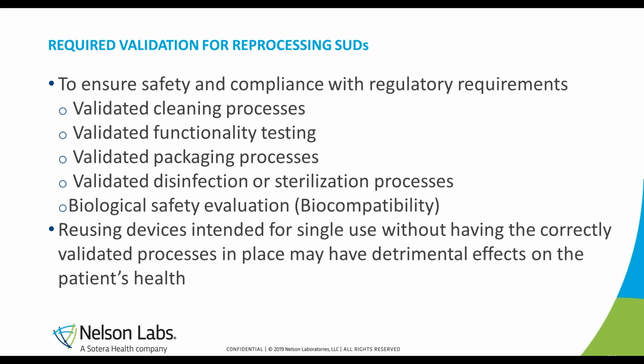A validated function test is commonly paired with validated cleaning and disinfection or sterilization processes to ensure the safety and efficacy of the reprocessed device. The expectation is that the third-party reprocessing firm follow the life cycle of an original device, including packaging validation and biocompatibility testing. So again, to repeat, failing to have these validated processes in place may have harmful effects on the patient's procedural outcome, as well as expose the firm to regulatory impact.